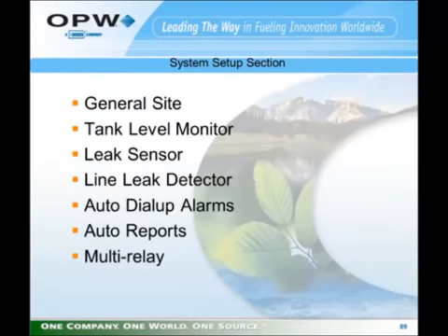The major menu selections under the system setup or general site setup: that's where you program in your name and address, communications parameters, things that affect the whole site. Tank level monitor, all the settings that you program for the tank level monitor portion, leak sensor portion, line leak detector portion, auto dial-up alarms. If you want to use the modem to dial up another device, you can program the unit to dial out on any programmed alarm or trouble that you choose. Auto reports is where you would print out automatic reports to be generated multiple times a day or on a daily basis, and multi-relay programming, where you would program relays to activate on the alarms or troubles that you choose.